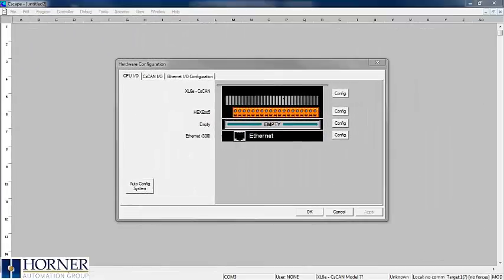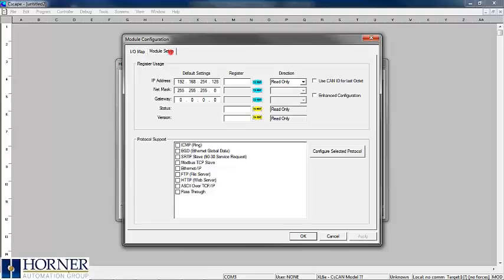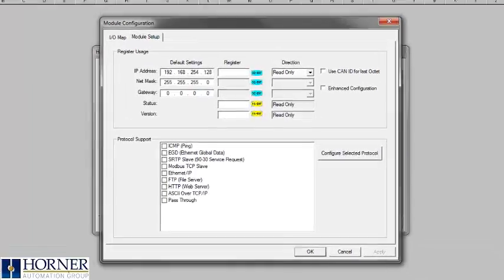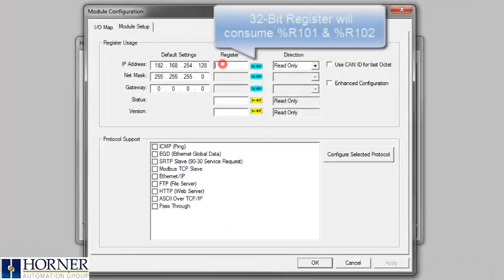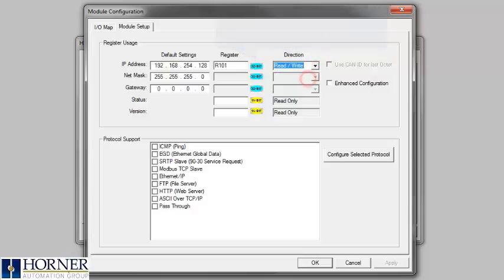We will start in the hardware configuration and select Config for Ethernet. From here we will assign a 32-bit register for the IP address and choose the direction of read-write. This will allow the user to change the IP address by changing the value of R101.